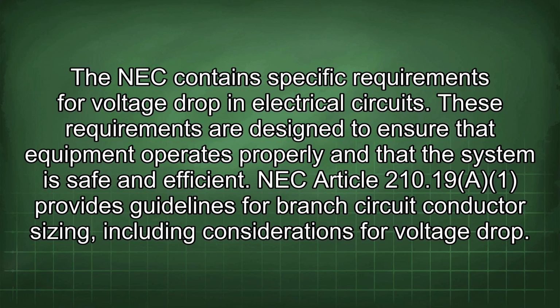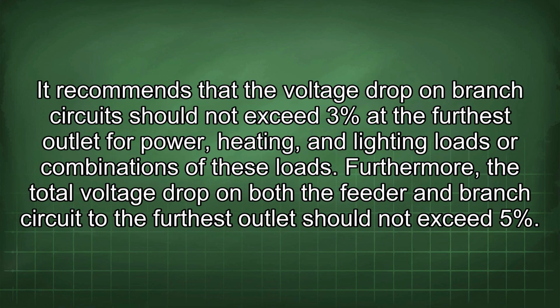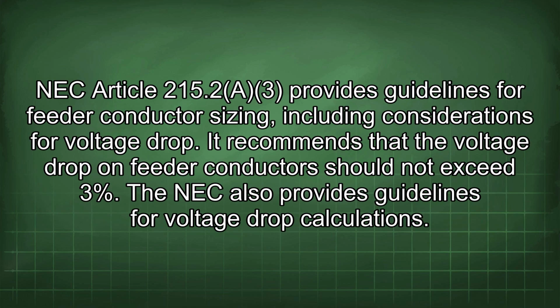NEC Article 210.19(A) provides guidelines for branch circuit conductor sizing, including considerations for voltage drop. It recommends that the voltage drop on branch circuits should not exceed 3% at the furthest outlet for power, heating, and lighting loads or combinations of these loads. Furthermore, the total voltage drop on both the feeder and branch circuit to the furthest outlet should not exceed 5%. NEC Article 215.2(A) provides guidelines for feeder conductor sizing, including considerations for voltage drop. It recommends that the voltage drop on feeder conductors should not exceed 3%.